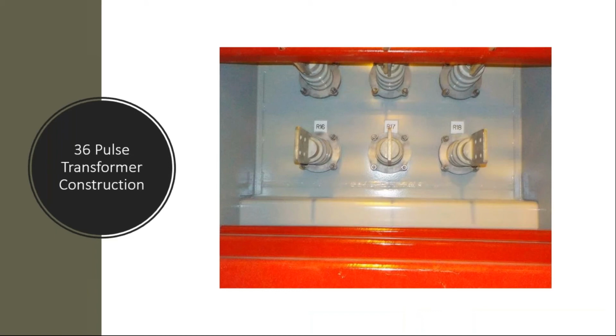This is a picture of the same 36 pulse transformer, and you will find the LV ATC has 18 bushings. They are very low voltage because the voltage, as I said, is lower with high current, and you'll see 6 sets of bushings with three phases. Most of the time it's difficult for the customer, so we work very closely with the customer to ensure the cables they are going to bring in are aligned up to the bushings. They are stepped out, sometimes with a bus bar, sometimes just a bushing by itself, and the cable we supply requires supporting, like the red FRP channel which you see on top and bottom. They support the cables so the bushings do not see a whole lot of cantilever load. This is a small portion of the 18 bushings in the same ATC.